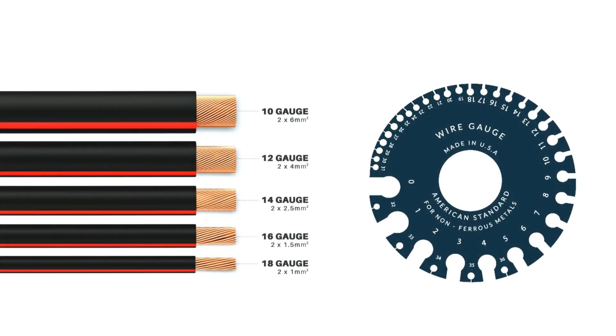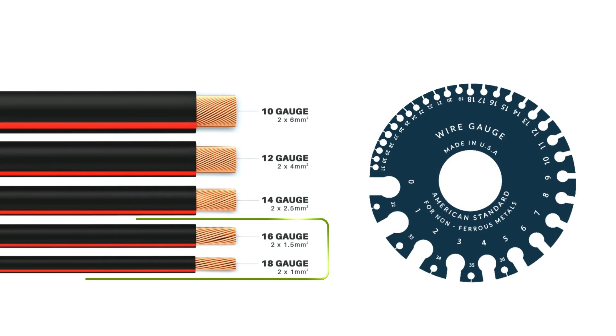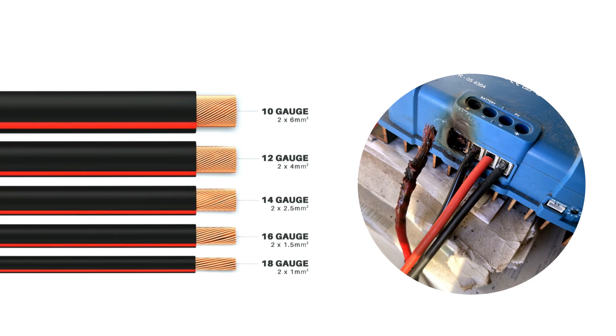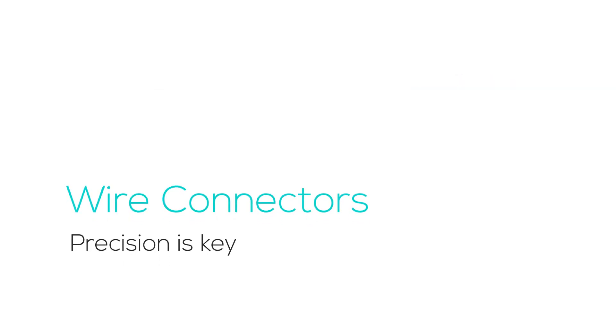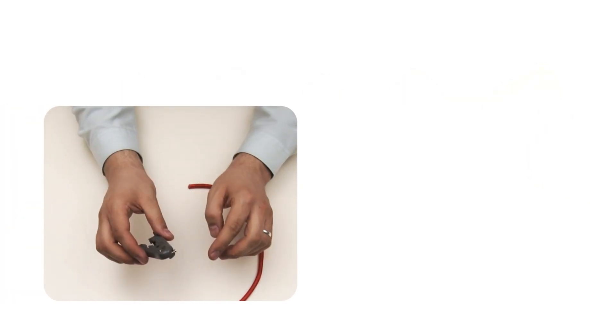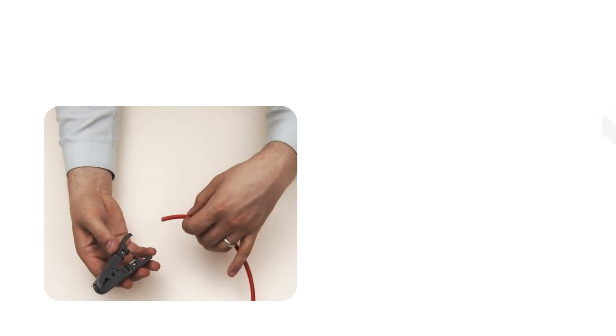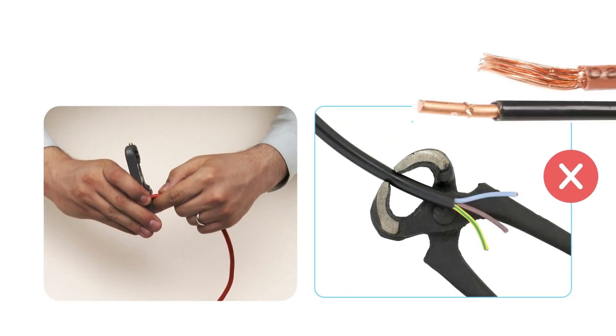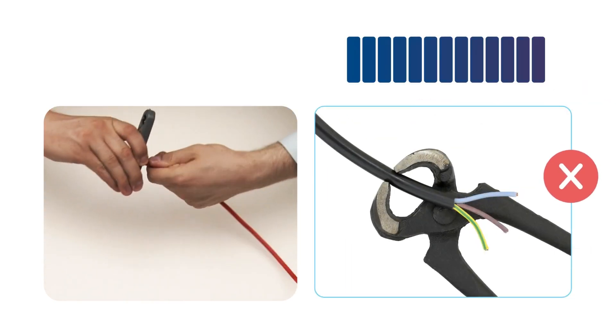Wire gauge — essentially how thick the wire is — and its length are both very important. A wire that's long and thin can resist the flow of electricity, and if this resistance gets too high, it not only causes more energy loss but can even lead to fires. Besides cables, elements like cable lugs and proper tools are needed. It's vital to strip insulation with precision, so specialized stripping tools are recommended. Always avoid using inappropriate tools, which can compromise connections and lead to overheating.